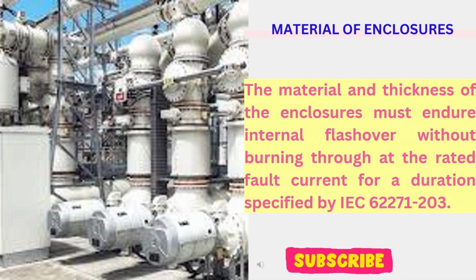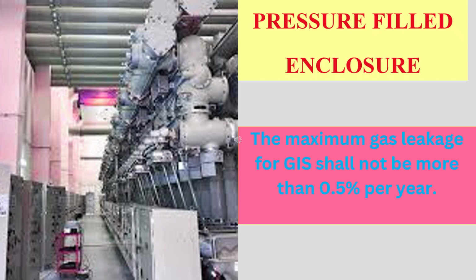5. The material and thickness of the enclosures shall withstand the internal flash over without burn through at rated fault current for a period as per IEC 62271-203. Each pressure-filled enclosure shall be designed and fabricated to comply with the requirements of the applicable pressure vessel codes and based on the design, temperature and pressure as per relevant IEC. The maximum gas leakage for GIS shall not be more than 0.5% per year.